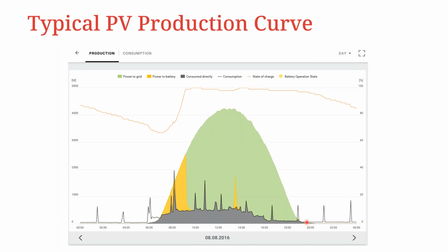the evening. With the presence of a smart meter, Fronius smart meter, we can see what is the portion of consumption throughout the day, but more importantly, what is being consumed during the period when you have PV production. So as you can see, we have what is power to the grid, which would mean for our case, this would be excess power. This in yellow here is power to the battery, and in black here is what is consumed directly. And then the black line shows us consumption during the day and night. And then the orange line is the battery state of charge, and then the battery operational state.